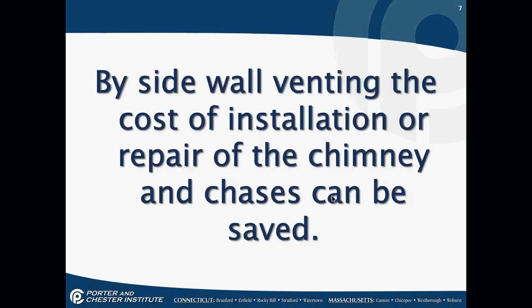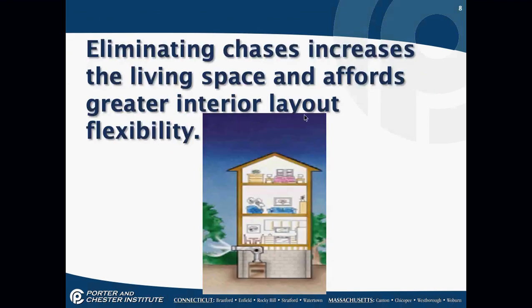This is called sidewall venting, is another word for this. We don't anymore have to worry about repairing the chimney. It eliminates all the chaseways and everything through there and gives much more living space because I don't have that chimney going up through the center of the house. So again, we have our boiler or furnace down here in the basement. We have our vent pipe connected to a power venter. And we have the exhaust that goes outside the house.